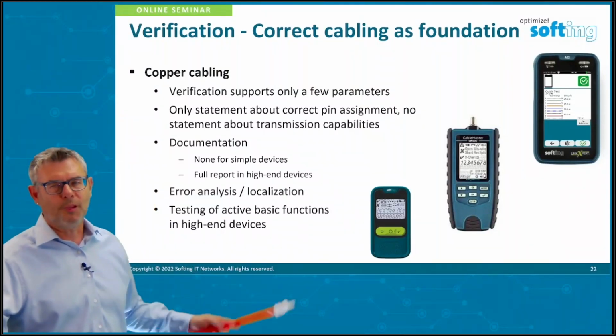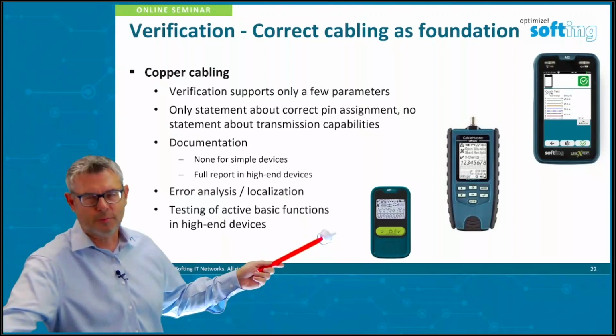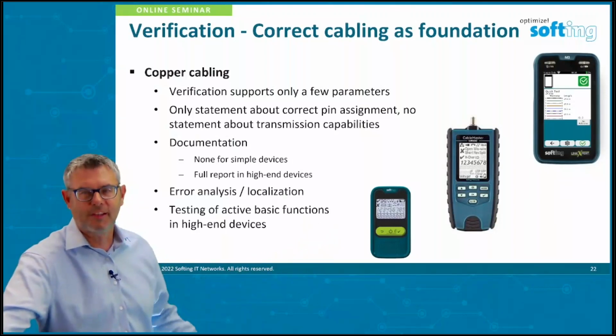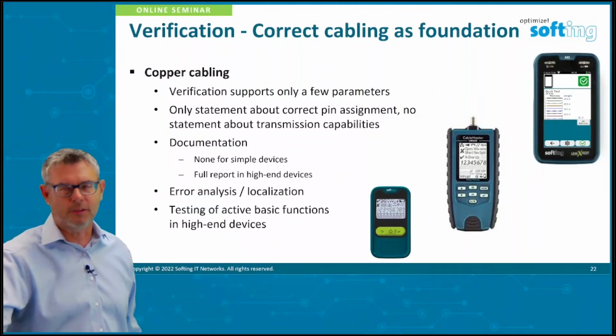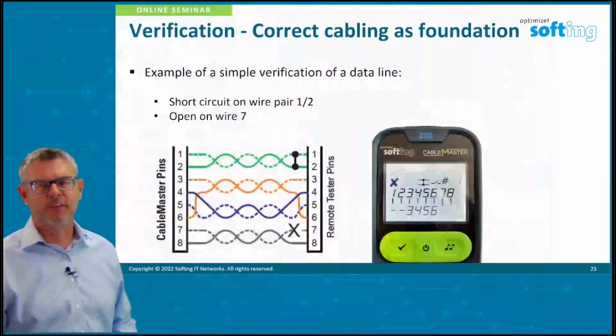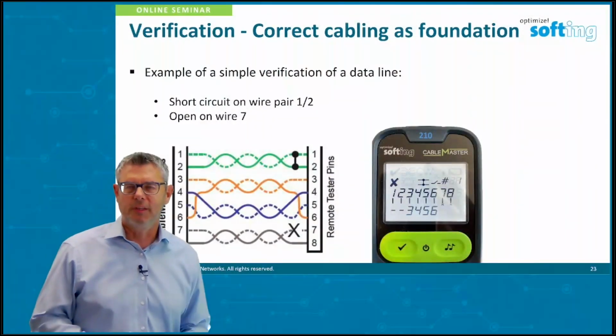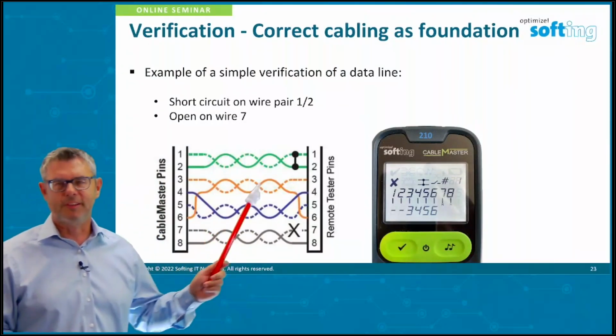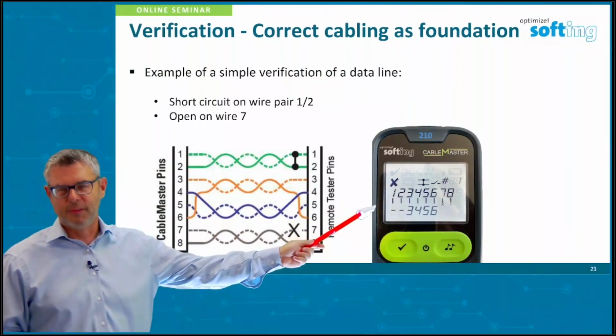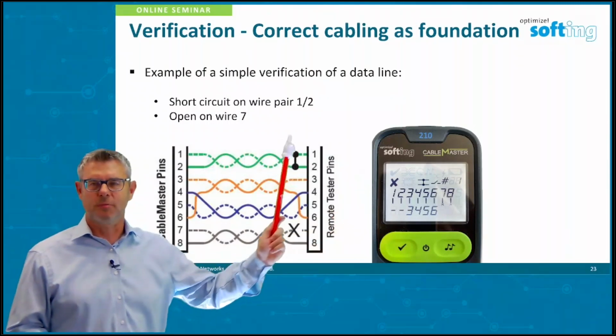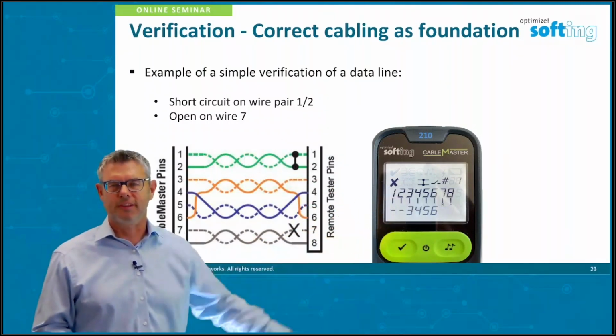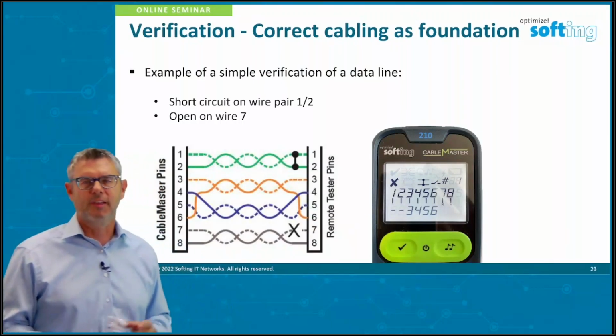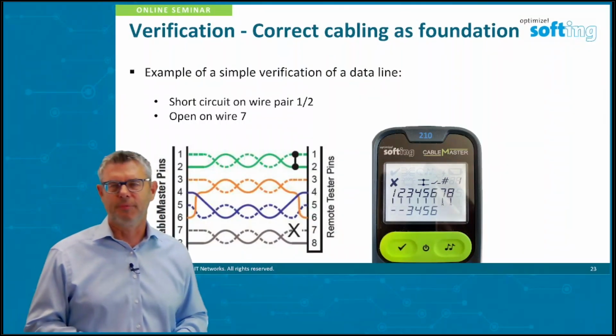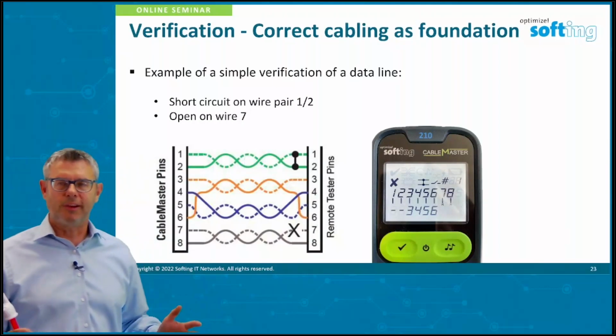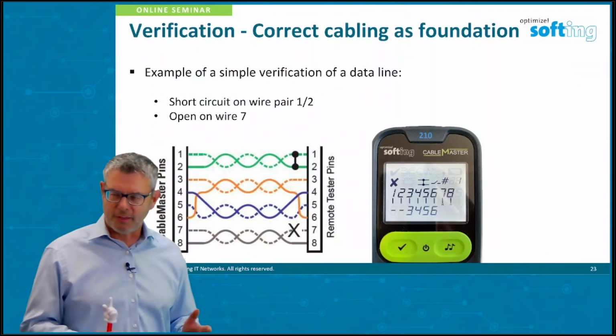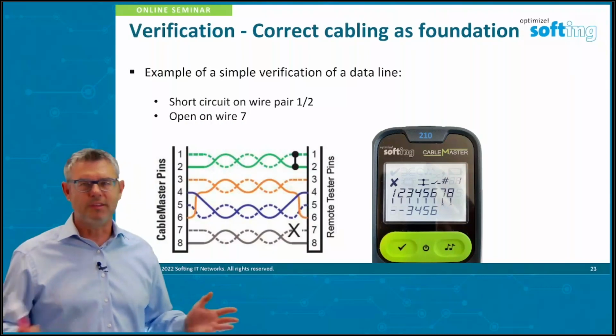People tend to love this instrument because it's about 60 euros, something like this. And it gives you a statement about whether the wiring is correct or not. Here you see the sample. This is the scheme, and this is how it's reported on this tester. You see 1 and 2 is shorted, 7 and 8 is just open, is missing, it's always pairwise, and the other pairs in between are working fine. So that's a statement where you can start to search for faults. But the big problem you get now is you don't know where the fault is.